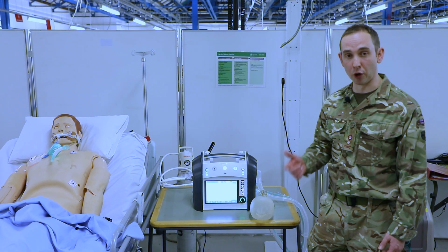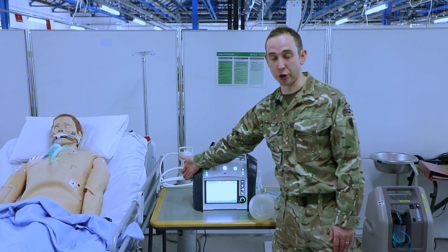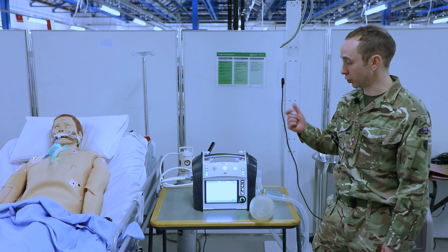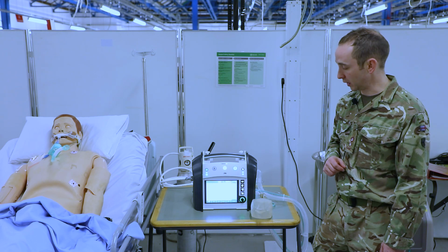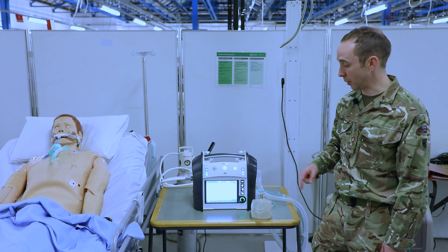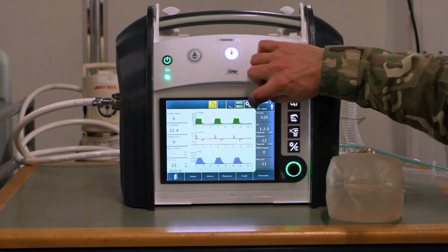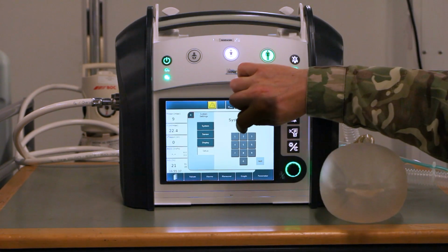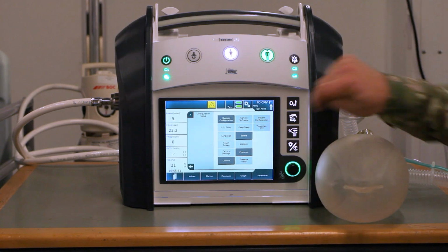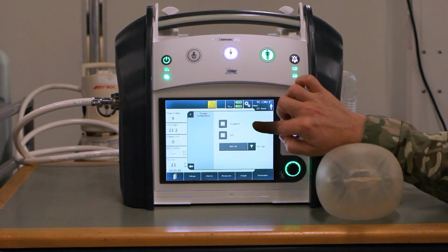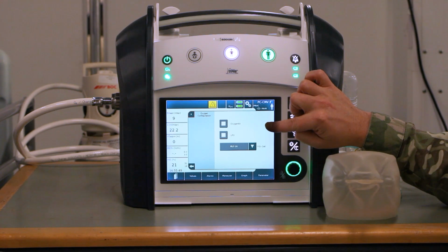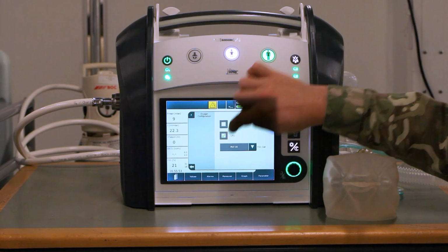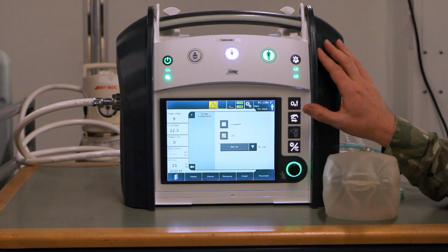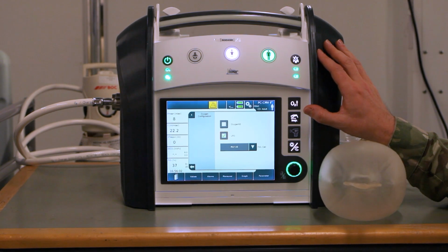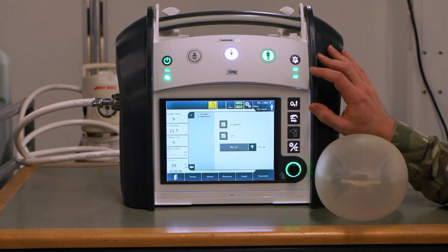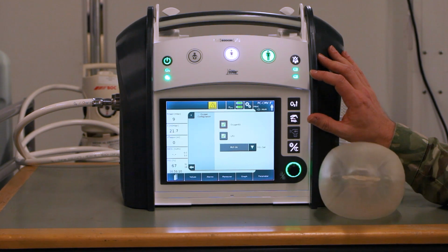So as previously stated, we can deliver oxygen in different ways. We can either use high pressure oxygen using the high pressure oxygen hose, or we can use low pressure oxygen using the low pressure oxygen adapter. But to ensure that happens effectively, we need to go into the settings menu to determine which way we're delivering that oxygen. So we will click on the settings button, go to setup, put in the code, which is 1968, click next, and then we'll click oxygen configuration. When both of these are deselected, this is set up for high pressure oxygen. If we want to use low pressure oxygen, we will tick LPO, and this will allow us to deliver low pressure oxygen from a cylinder using some bubble tubing. If we're going to use an oxygen concentrator, we also need to click the oxygen 93 button to ensure that we are telling the machine that we're using an oxygen concentrator.